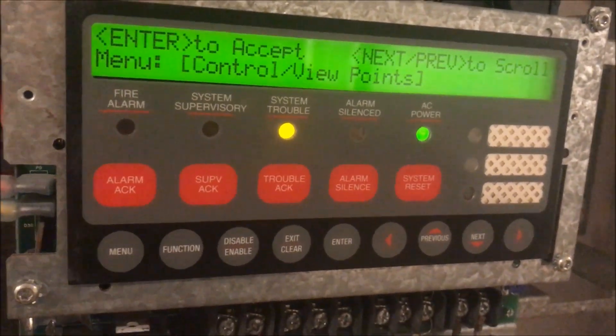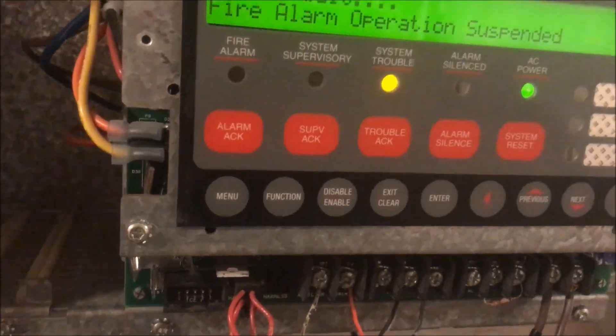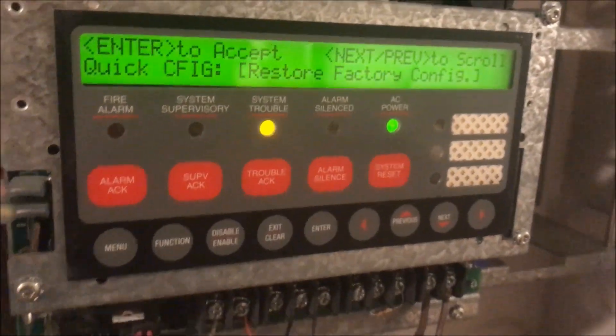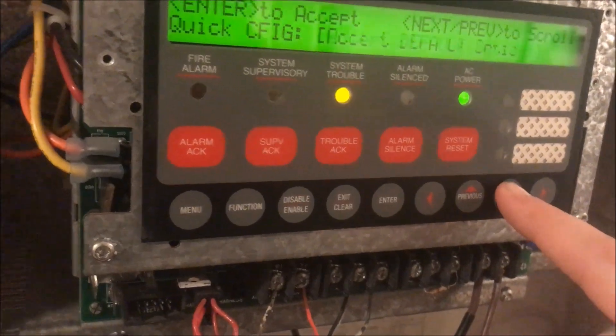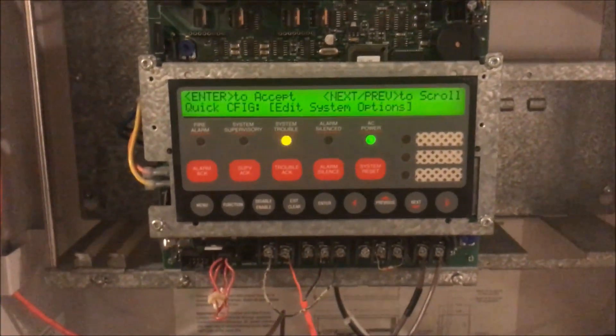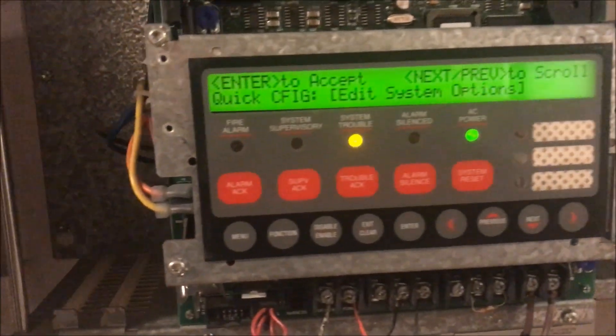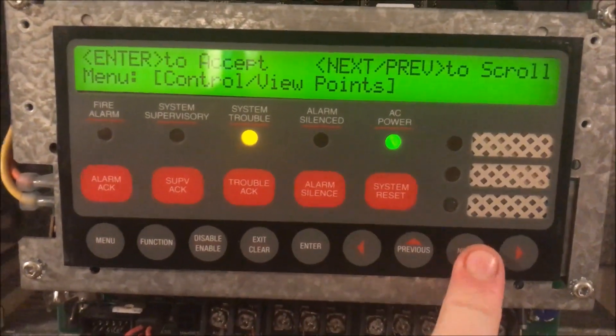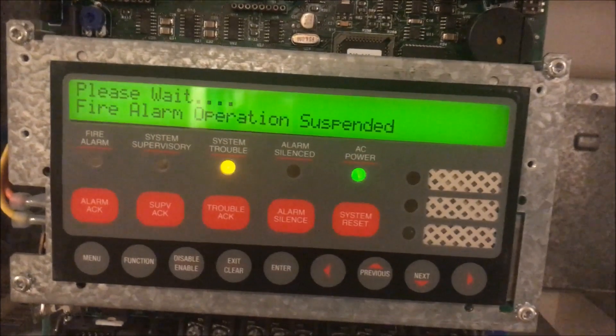In level four you can do everything from previous levels, plus quick configuration, and edit your system options — things like NAC cadence, what you want doors to do with no power, what you want alarms to do with no power, how long the panel sits before you can silence it, how long before it silences itself. Basically all your system preferences.